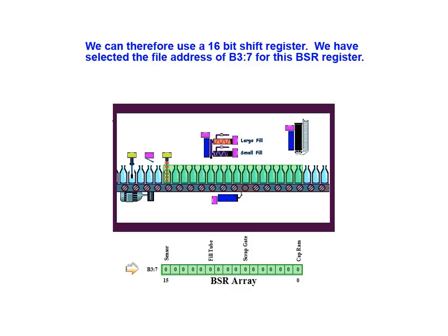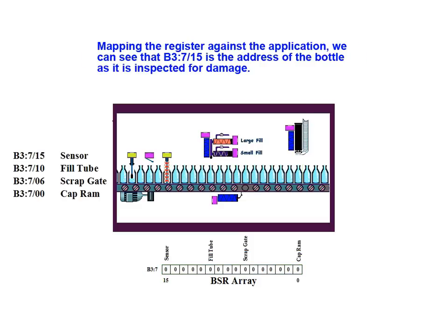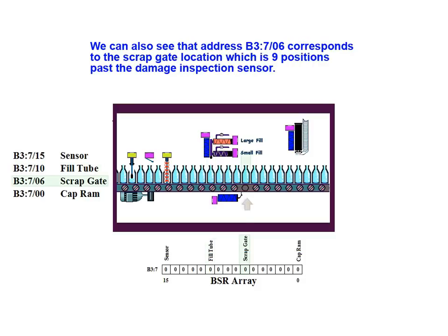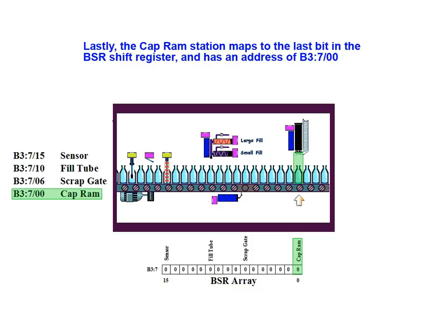We have selected the file address of B37 for this BSR register. Mapping the register against the application, we can see that B37-bit 15 is the address of the bottle as it is inspected for damage. The fill station location corresponds to address B37-bit 10. Address B37-bit 6 corresponds to the scrap gate location. Lastly, the cap ram station maps to the last bit in the BSR shift register with an address of B37-bit 0.